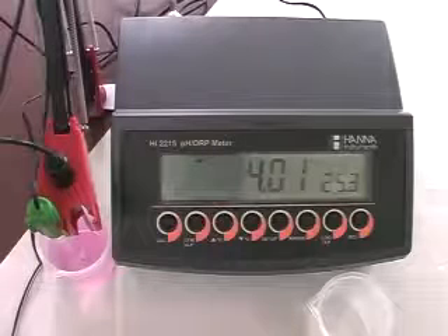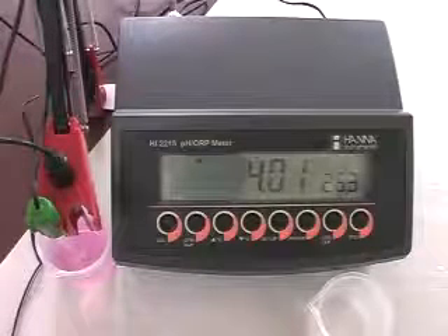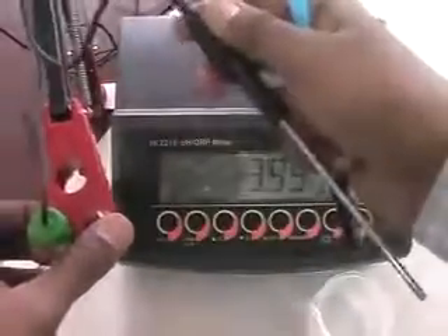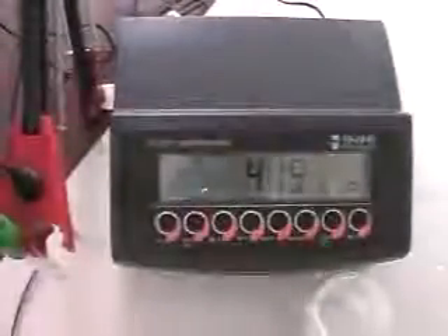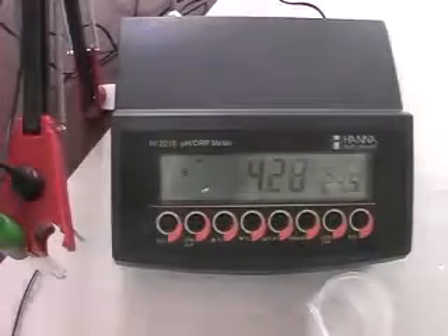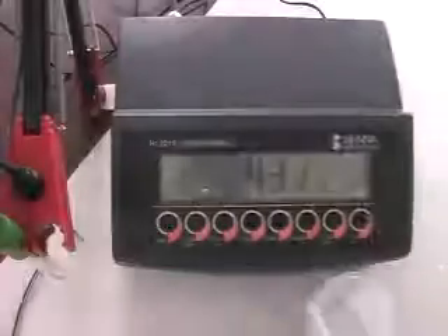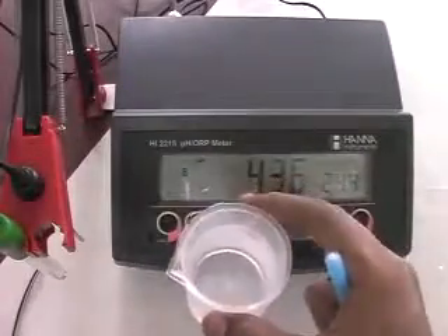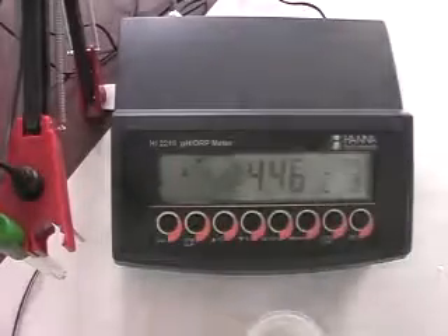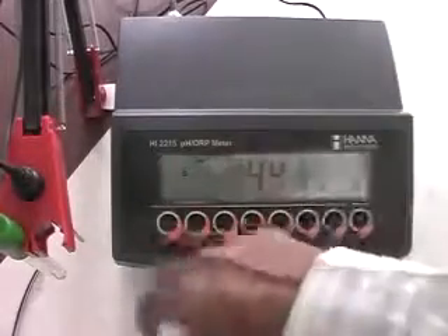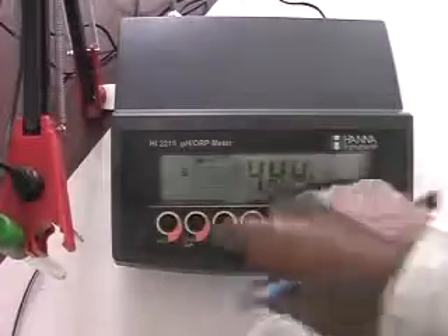First, check all the required accessories. Make sure that your electrode and the temperature probe is connected to the meter. Connect the pH electrode and temperature probe to the meter. Then take pH 7.01 buffer sample, pH 4.01 buffer sample, distilled water to clean the electrode. Make sure that all your buffer samples are fresh.